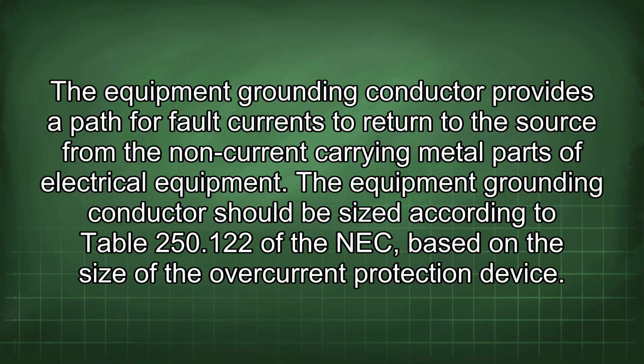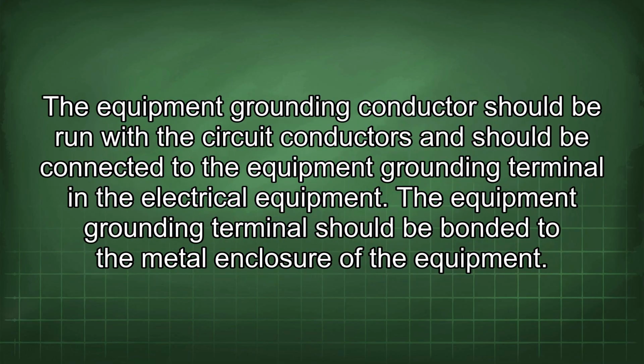250.122 of the NEC, based on the size of the overcurrent protection device. The equipment grounding conductor should be run with the circuit conductors and should be connected to the equipment grounding terminal in the electrical equipment. The equipment grounding terminal should be bonded to the metal enclosure of the equipment.